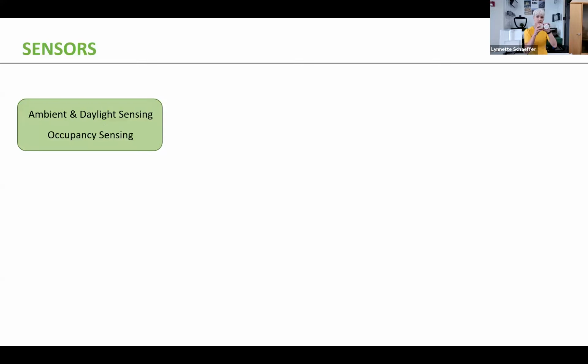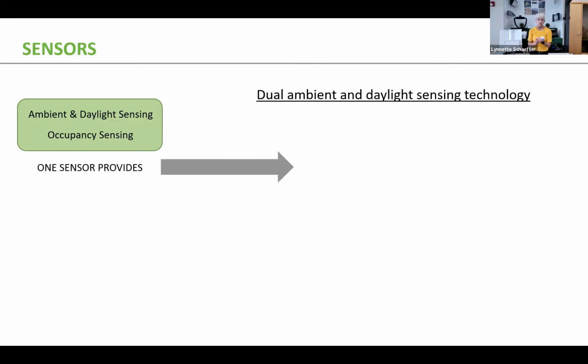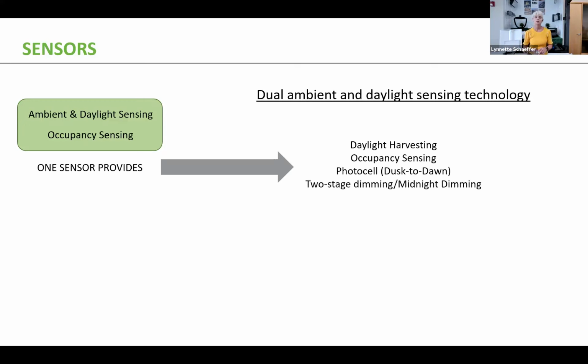So one sensor, either the PIR or the microwave, doesn't matter, gives you dual ambient and daylight sensing technology. That means you've got daylight harvesting, occupancy sensing, photocell (aka ambient or just basic photocell), and two-stage dimming / midnight dimming, which basically means if the sensor turns on at say 6 p.m., it stays on until about 6 hours later, so it'll go off at midnight. That's called two-stage dimming or midnight dimming. So one sensor does everything you want it to do.